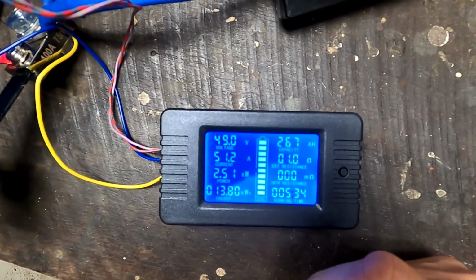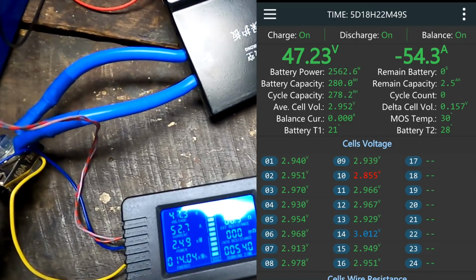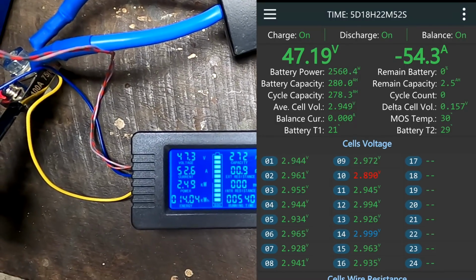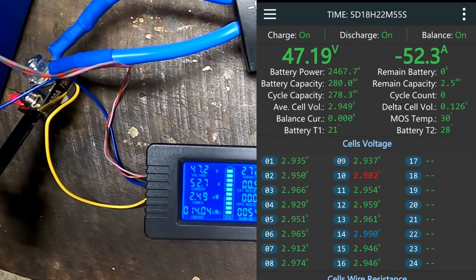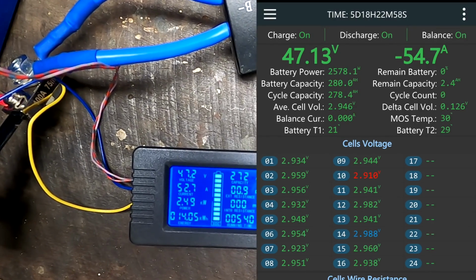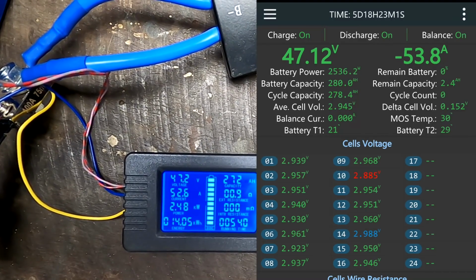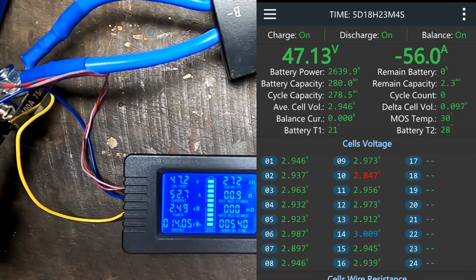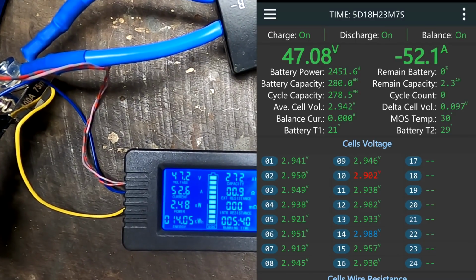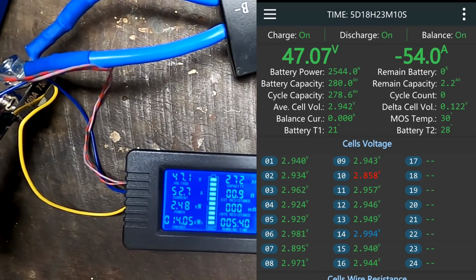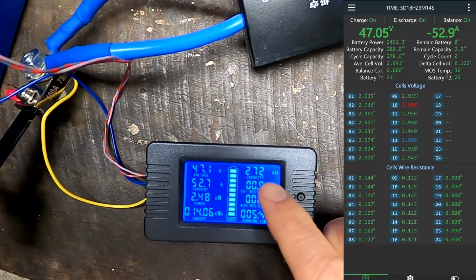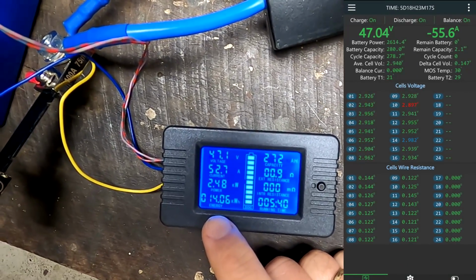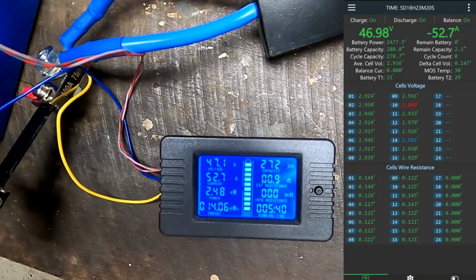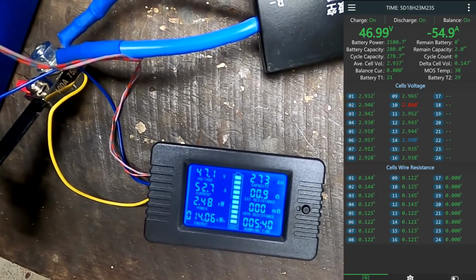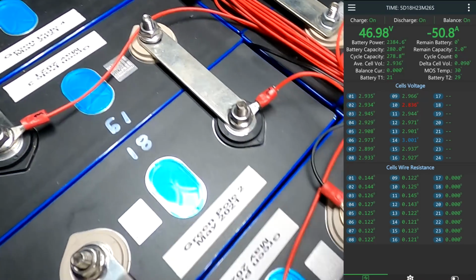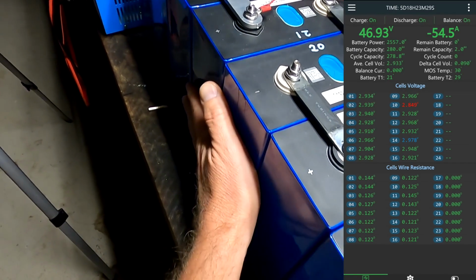Nice. And it's still going. So I think we are coming very close to an end now. All cells are under 3 volts now. You can see the overall voltage, 47 point something 2 volts, and it's dropping now. 0% remaining, 2.3 ampere hours as per calculation. So we've discharged 272 ampere hours so far, 14 kilowatt hours and counting. That is very nice. Battery temperature 29 degrees here inside this gap. And you can really feel it. It's nice and warm now, the battery.